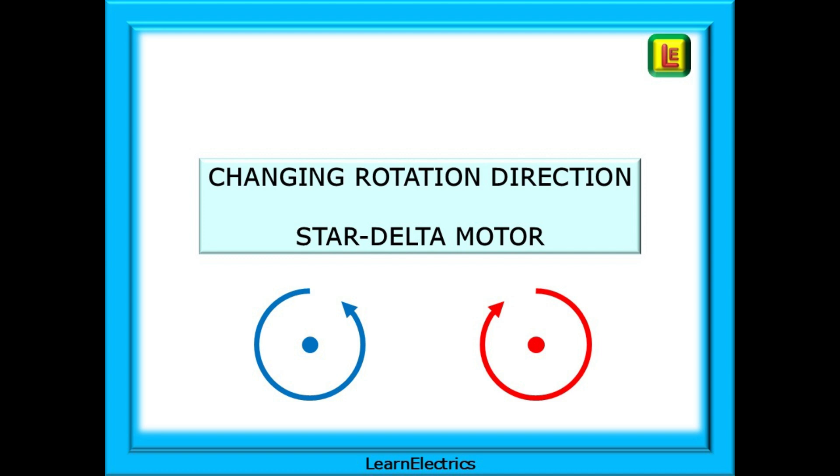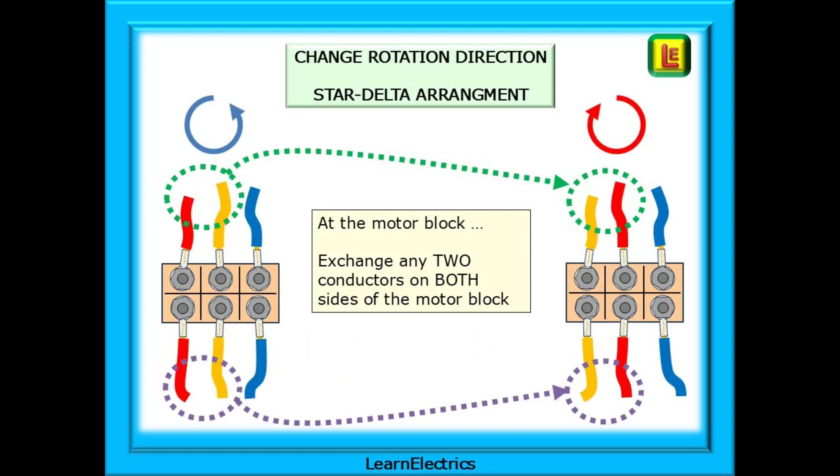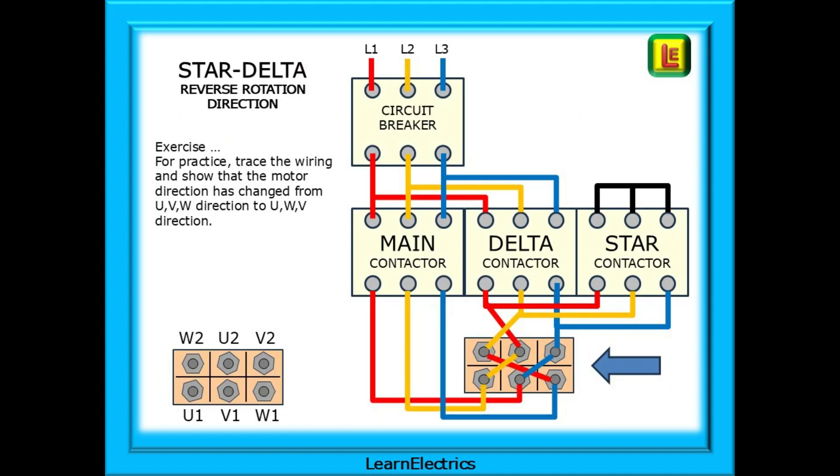And lastly, a frequent question: how do we change direction with a star delta starter? To change rotation direction with a star delta arrangement, there are three methods. As previously mentioned, I prefer to make my changes at the motor terminal block. To do this, exchange any two conductors on both sides of the motor block. In this example we've exchanged the red and yellow supply conductors at W2 and U2, so we must exchange the red and yellow supply wires at terminals U1 and V1. And here is that change of wiring shown at the motor block. For practice, trace the wiring and show that the motor direction has changed from UVW direction to UWV direction, and I'll leave that one with you. Pause the video and follow the wiring.